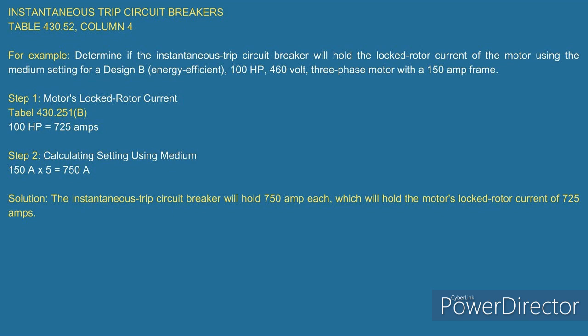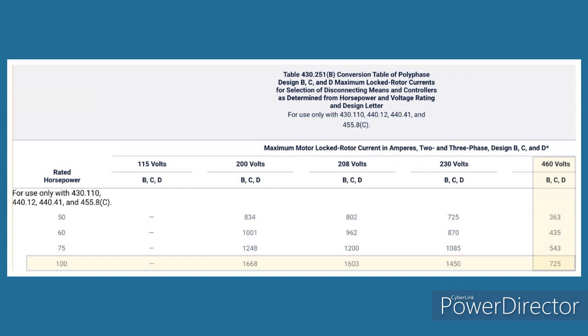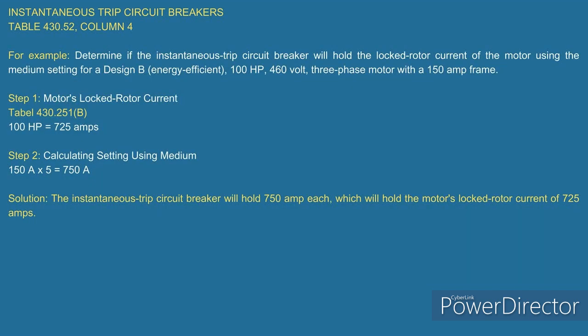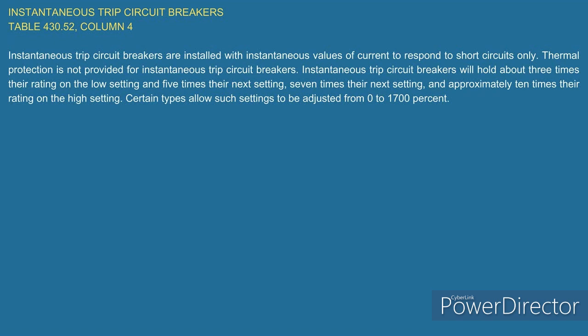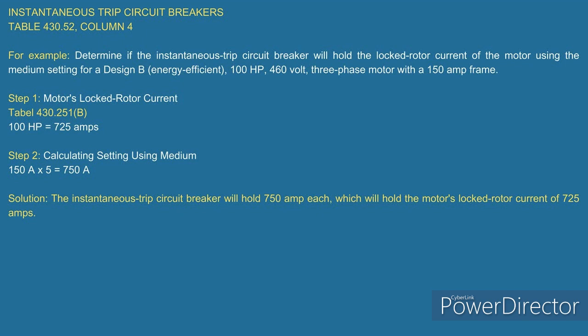Now, if I come back and pick up 100 horsepower here, and come across for that Design B 460-volt three phase motor, it tells you the inrush current here is set at 725 amps. Now, watch this. On the medium setting, let me go back so everybody can see this one more time. It says on the low setting and 5 times their rating on the next setting. We're going to call that 5 or 7 times, but we're just going to check the 5 times because we're doing it on a 150 amp frame. True. Now, watch this. I take 150 amps times 5, which gives me 750 amps on the medium setting, which is enough to hold that locked rotor current of 725 amps.